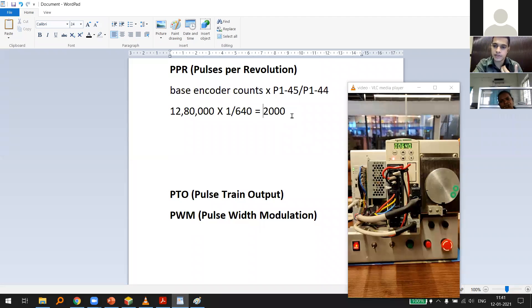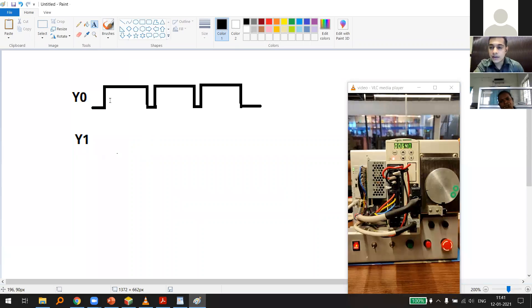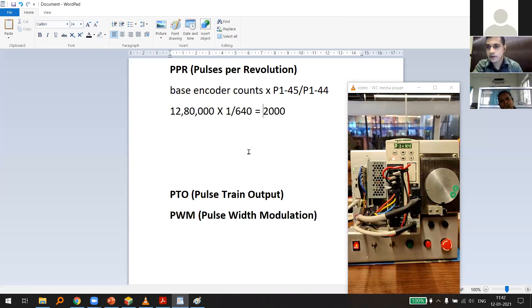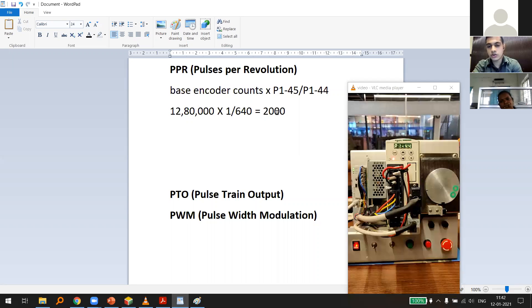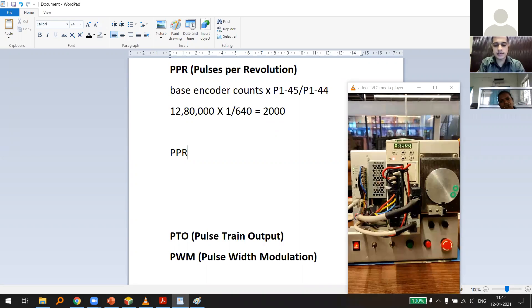This means as a programmer: if I give 2,000 pulses from Y0, this servo will rotate one full revolution. Understanding PPR is very important even when programming robots. The significance of PPR is that it determines resolution — the smallest unit by which you can move your servo.